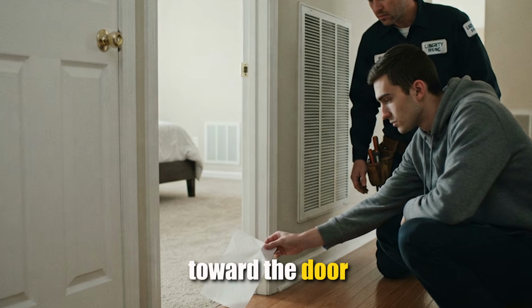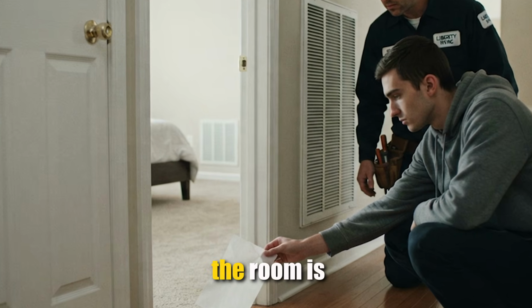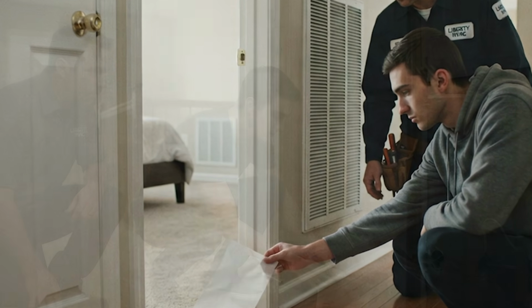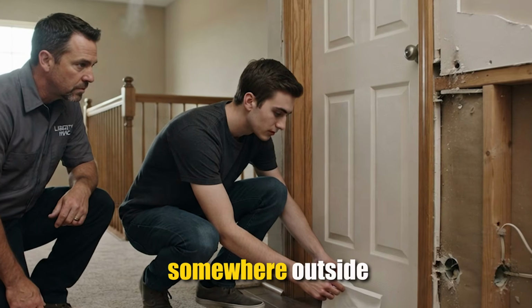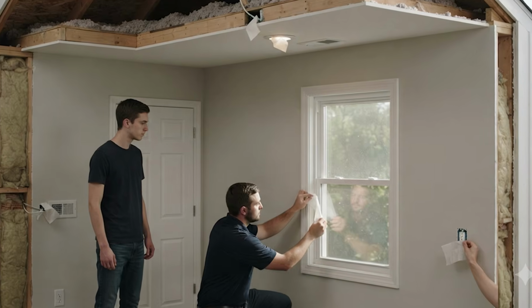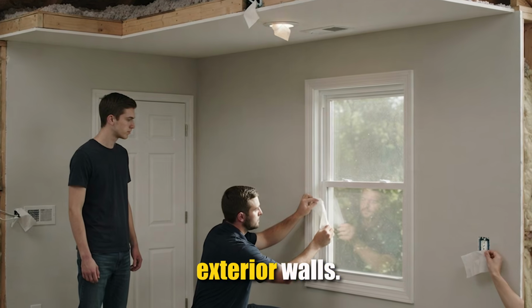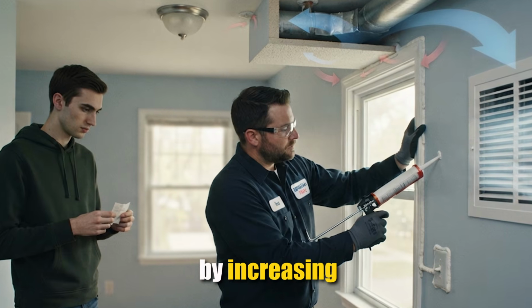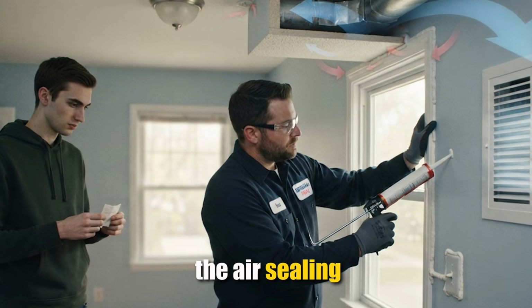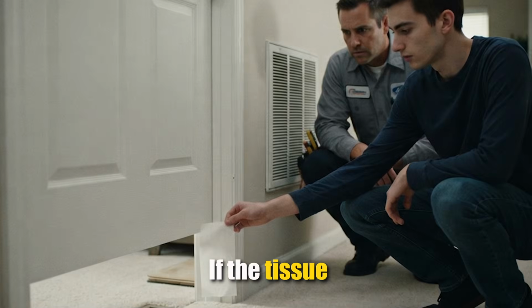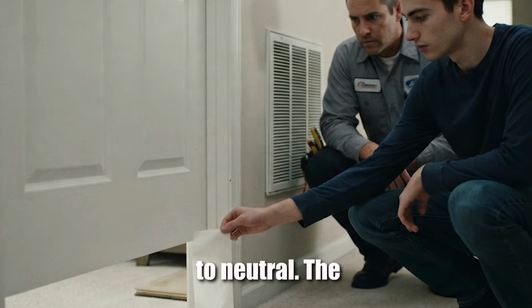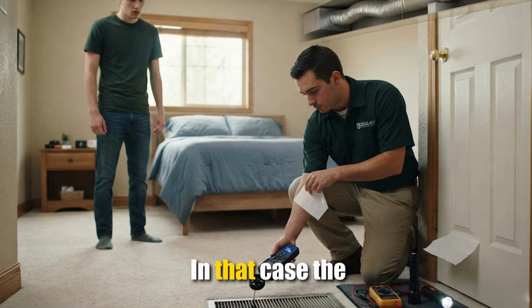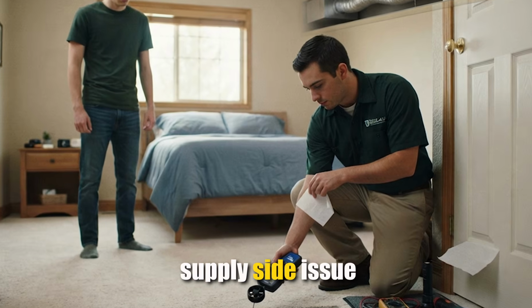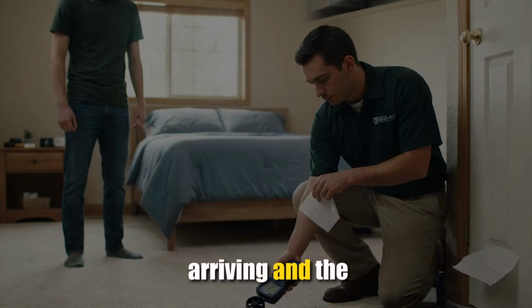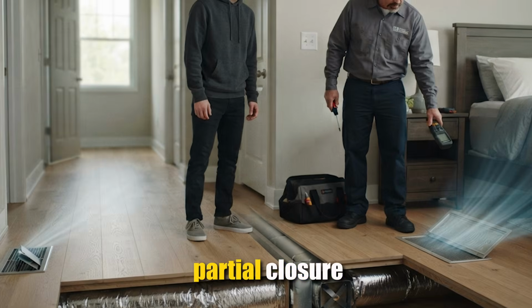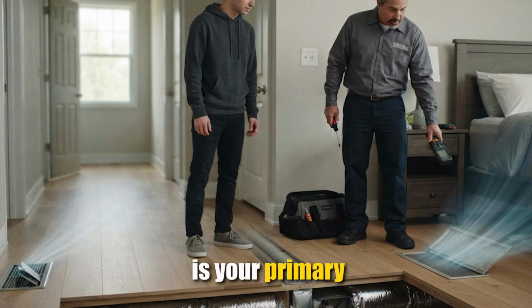If the tissue pulls toward the door, being drawn from the room into the hallway, the room is negatively pressurized relative to the hallway. This tells you the room is drawing air from somewhere outside the system: gaps in the ceiling, around windows, through electrical outlets on exterior walls. The register fix still helps by increasing delivery from the supply side, but the air sealing work is also worth doing. If the tissue barely moves, pressure is close to neutral. The return air balance is reasonable. In that case, the hot room problem is primarily a supply side issue, not enough warm or cold air arriving. And the register replacement combined with partial closure of overserved registers is your primary fix.